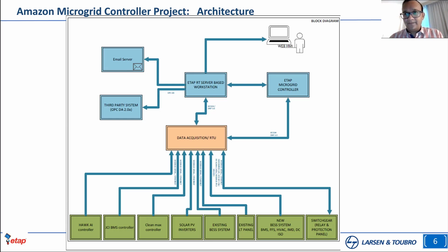We integrate that with the ETAP microgrid controller using IEC 104 and DNP3 protocols, and also with the ETAP real-time server-based workstation for SCADA purposes, again using DNP3 or IEC 104 protocols depending on the data set. It also provides the web HMI for operators, and has integration with third-party systems—existing or future—via the OPC DA 2.0A protocol.